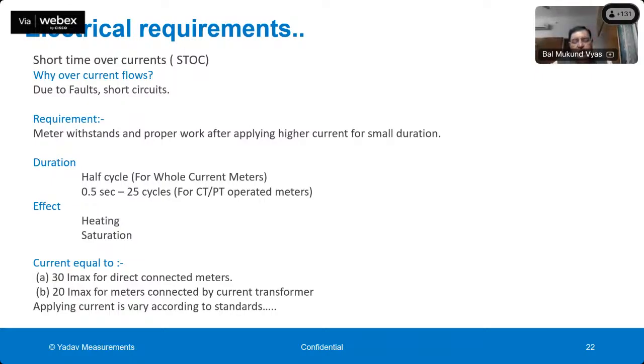There can be a fault in the electrical network in our house or in our industry. When there is a fault, a heavy current flows through the electrical network, and the same current is passed through the meter also. So it should not happen that if there is a short circuit in our house, the meter gets damaged or its accuracy is affected. A short circuit is created, and the short circuit current is passed through the meter, which is half cycle for whole current meters and 0.5 second, or say 25 cycles, for CTPT operated meters. It is checked that the meter is not causing any fire and is not damaged, and after the short circuit, the meter's accuracy is not affected beyond a particular limit which is specified in the standard.